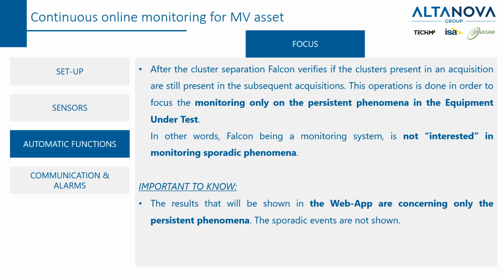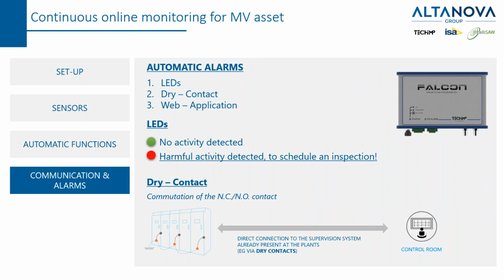The web app is one of the benefits of the unit, because it allows any operator with a laptop or even a smartphone with a simple browser to go inside the unit and check, at different levels of detail, the status of the equipment under test. As for the alarms provided by the unit, there are local alarms, just looking at the frame, provided by LED according to a very simple layout: green, no activity; red, there is an activity and it requires inspection. Or also using dry contact. And the last level is connecting through the web application using the Ethernet cable and checking all the functionality and seeing the severity of the alarm.